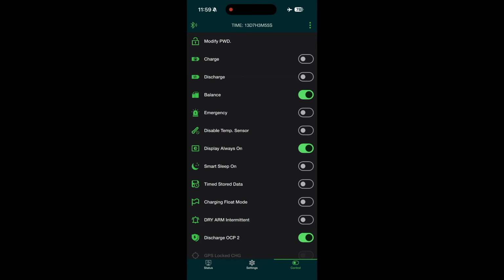Disable the temperature sensor. The BMS has a couple of temperature sensors, and if you turn this on, it will ignore whatever those sensors read. This is probably useful if you find your temperature sensors are faulty and it's not allowing charge to go in and out of the bank. Apart from that, I'd always leave it off, so your temperature sensors are always working.